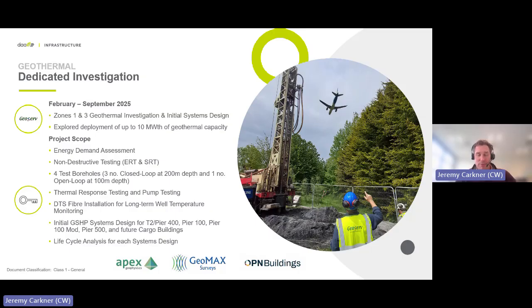We were looking to deploy a 5th borehole, but we ran out of time and viable space to do that, so that's why we ended up with 4 test boreholes. As I said, we did thermal response testing, pump testing, and one of the things that was included was also DTS fiber installations.